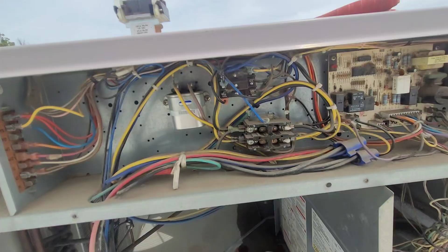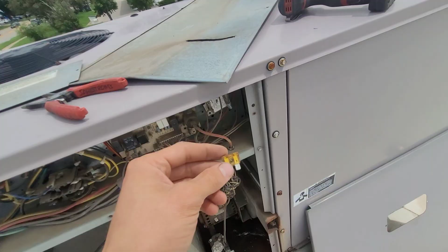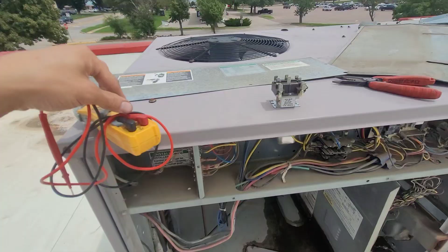However, you can see our main contactor is snapped in. Now I actually have the power off to this thing right now. So it has 24 volts to it, but it wasn't bringing on the blower. Well, I found this burnt fuse, which is never really a great sign. So now I'm trying to figure out where the short in the system is. But check this out. Coming from the unit with the power off, we should have no power.